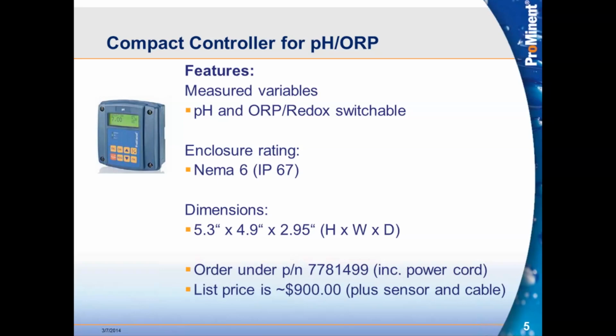Here we're going to order it by part number. Remember, it can serve both the pH or ORP sensor. You can order that by part number 7781499, and that will include a power cord, a power cord for 115 volt single phase. Okay, that's single phase input to it. So you saw in the previous slide that it can accept 230 volt as well. So if you have an application where you need it for 230 volt, just let us know. We can order that separately with a separate power cord and wire it in for you.